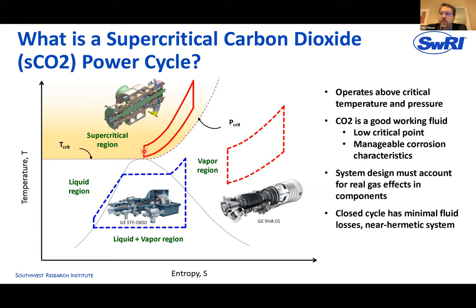CO2 in particular is a fluid that is attractive for operating in supercritical CO2 cycles. The reasons are that the critical temperature is fairly close to ambient temperature, so you can operate near the critical point with ambient heat rejection. And that allows for high cycle efficiencies.